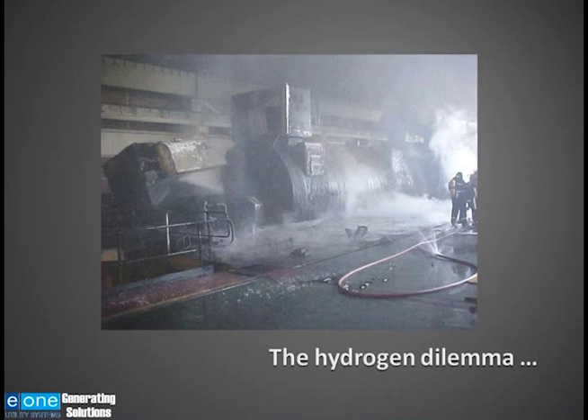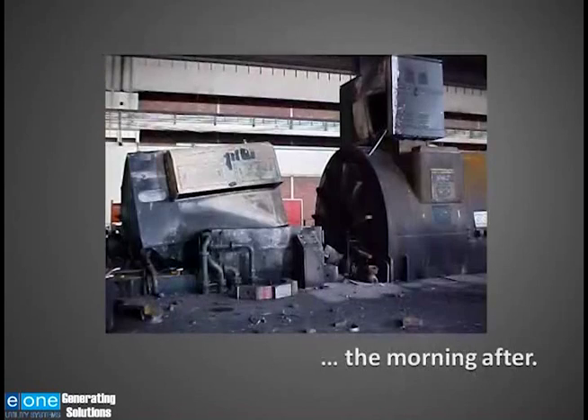This is what happens when you don't keep hydrogen inside the generator. I don't know the specifics of this failure. I do know that the seals broke down. There was a seal oil fire. There was also a hydrogen fire. The hydrogen actually caused the exciter cabinet to be blown off its frame. This is what you don't want to see the next morning coming into work. You can see where hydrogen escaped out of this generator, went into the exciter or collector cab, and blew the exciter or collector cab from its frame. This generator was totaled and could not be put back together.